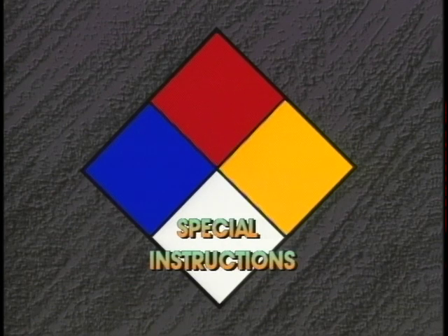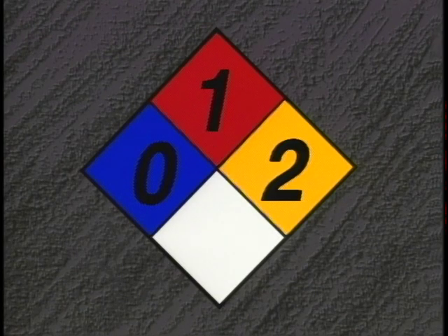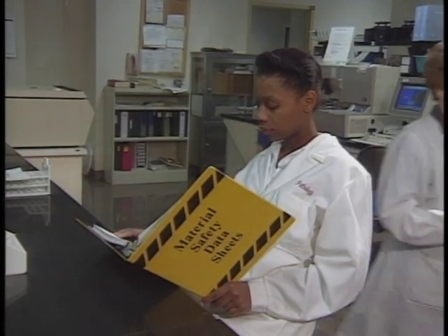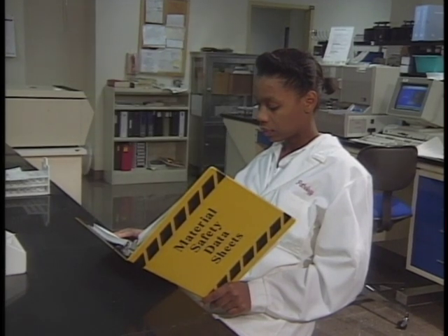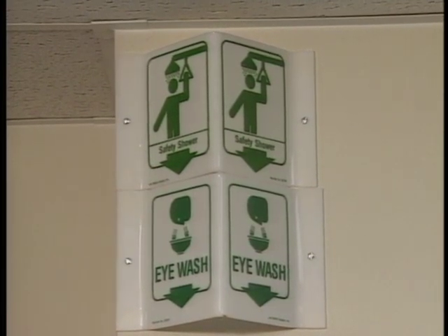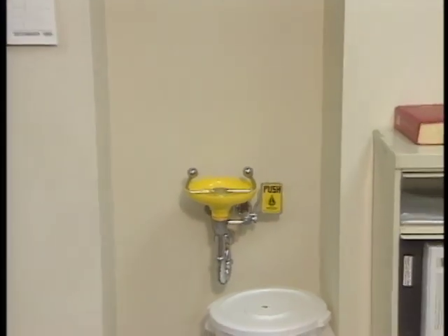White is reserved for special instructions. The numbers zero through four are used to indicate the degree of danger involved — zero meaning the risk is relatively low, and four warning that a serious danger is present when handling the material. You must have complete familiarity with proper procedures for the handling, storage, and disposal of hazardous chemicals. Consult your material safety data sheets for specific instructions. Never guess or rely on what you might remember from your high school chemistry class. Also, make sure you know where emergency eyewash stations and emergency showers are located, in case a hazardous chemical gets in your eye or on your skin. Learn how to operate these devices before an actual emergency occurs.